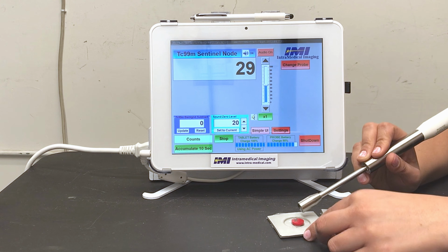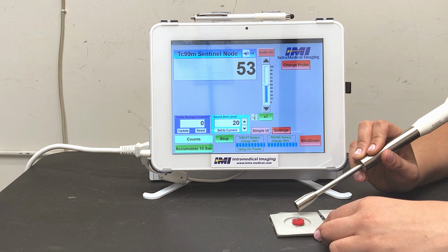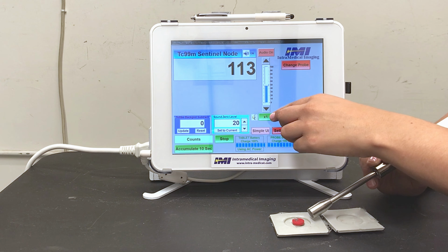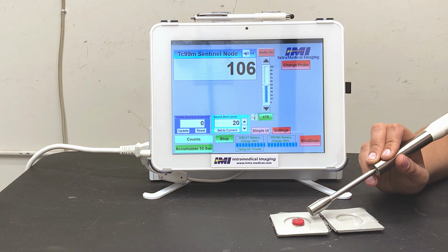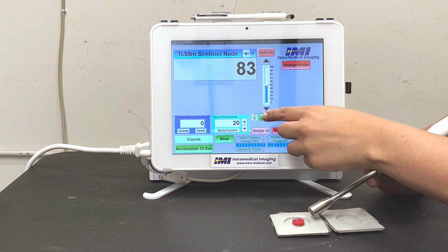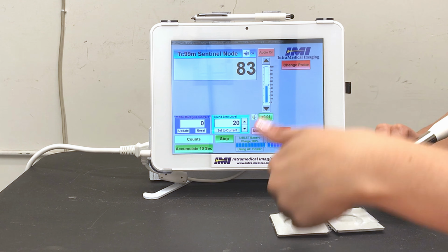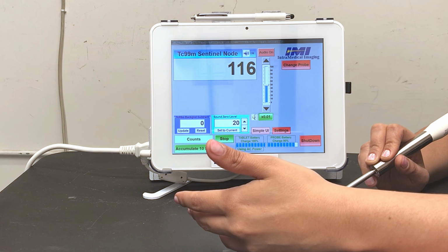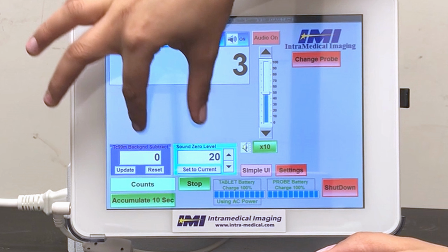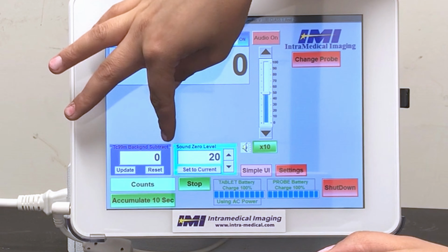Below the volume control, the green button labeled ×1 adjusts the sonification of counts per second. Pressing it to ×10 or ×100 helps surgeons hear the modulation better when they are further from the source. Other readily available features on the count menu screen are TC99 background count subtract in the indigo box and sound zero level in the light blue box.